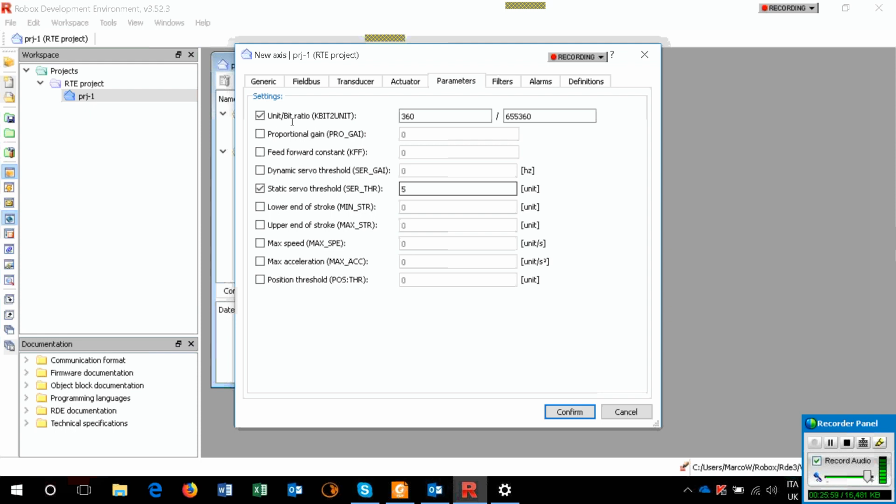So I have to set the parameters of gains, proportional gains, feed forward and so on, or tell the person in charge of doing that to perform the task, in order to never go beyond this maximum error. If it happens, it means we have problems. If we have problems, there is the alarm. Alarm number 11, you will always see this alarm, servo alarm system, number 11.